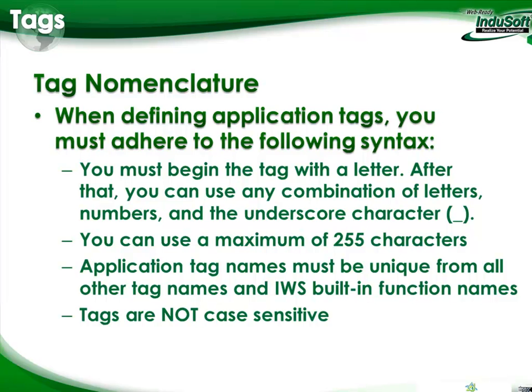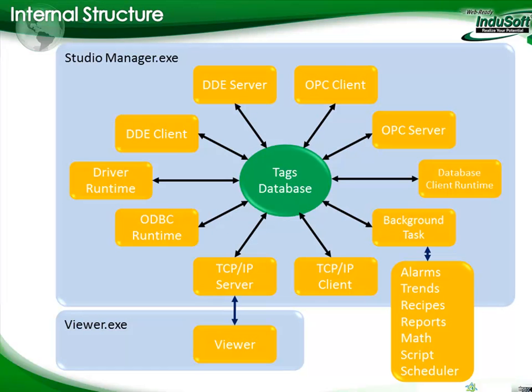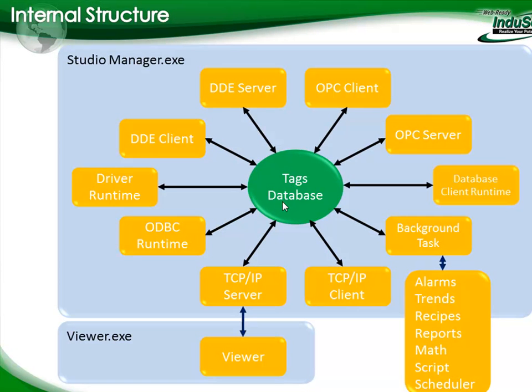Tag names are all pretty much internal. Going back to the chart — other HMI or SCADA packages may have the concept of internal tags versus external tags. Our tags are all pretty much internal in that if I have a tag on a screen being displayed, it gets its information from the tag database. If that tag is referenced in a driver worksheet, the real-world value comes in through the driver runtime, updates the internal tag, the screen updates, and all the information comes in through the tag database.